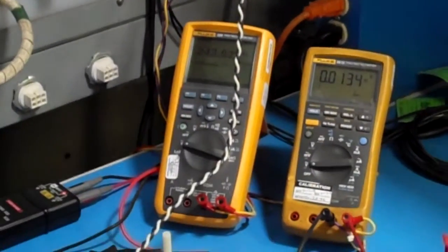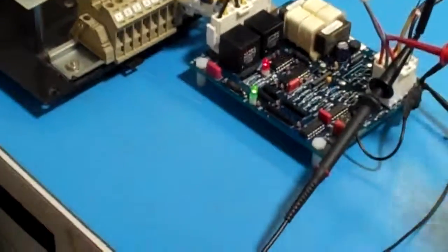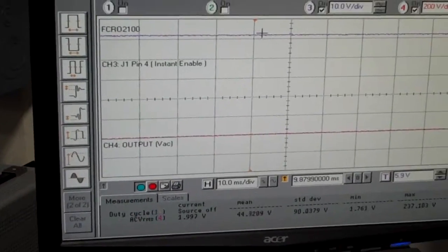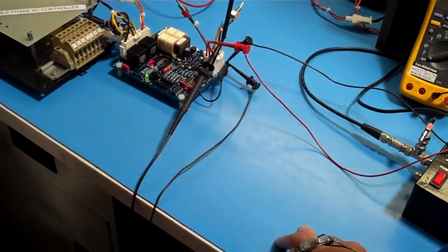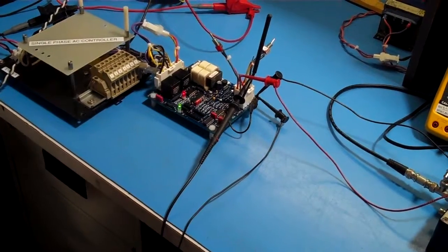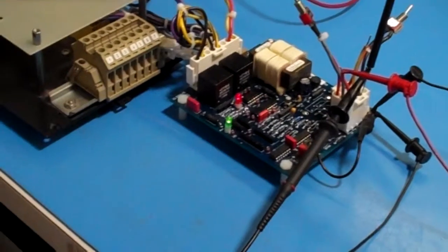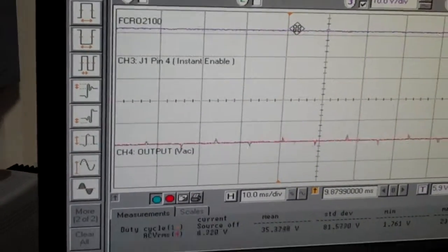Right now we have no output, and although the board, can we enable the board, Tony? Okay, we have the board enabled, but SIG high being 0, and there's a low signal inhibit signal, that it's not until that SIG high or voltage command signal gets to a certain threshold, about half a volt, we won't get any output. So I'm going to ask Tony to increase SIG high until we clear that red LED. Alright, wait right there. At that moment we're starting to see some output, and I'm going to ask you to start increasing SIG high now, Tony.